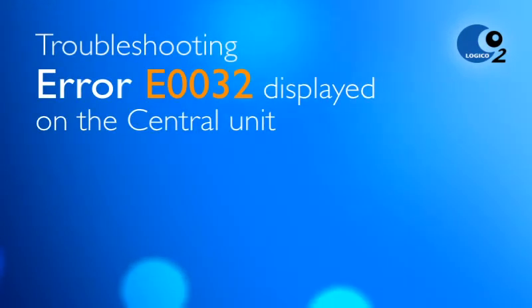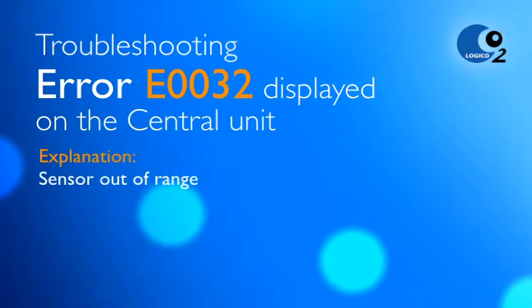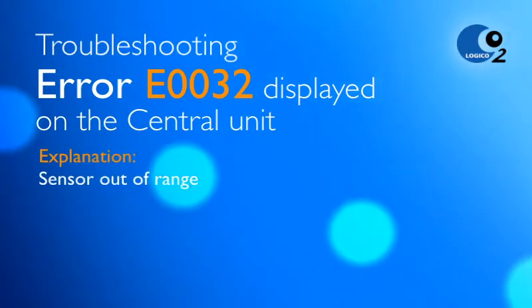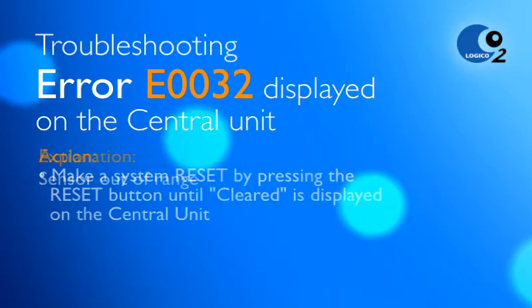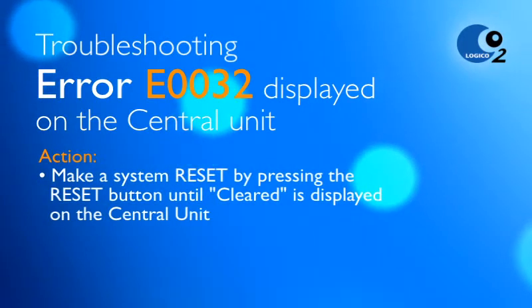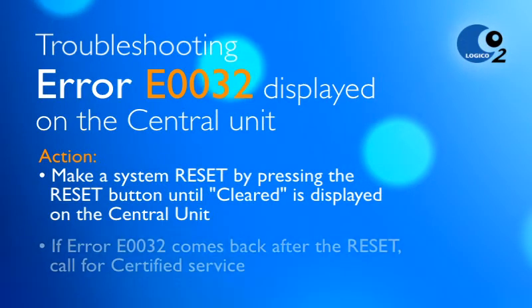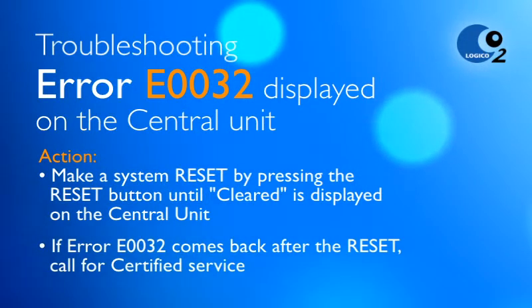If you have an error E0032 displayed on the central unit, the sensor is out of range. Make a system reset by pressing the reset button until cleared is displayed on the central unit. If the error E0032 comes back after the reset, call for service.